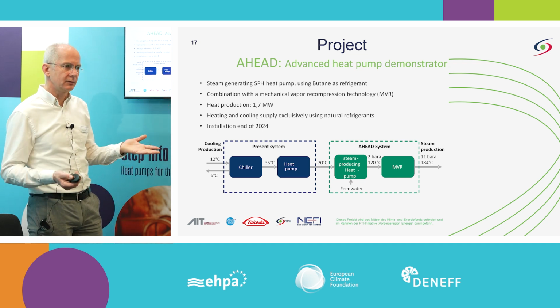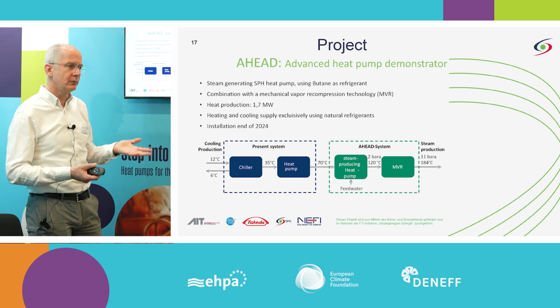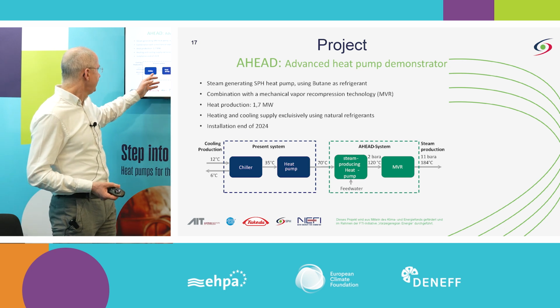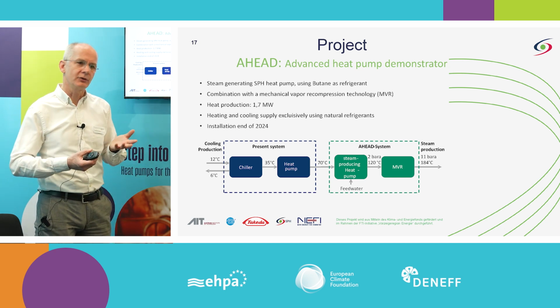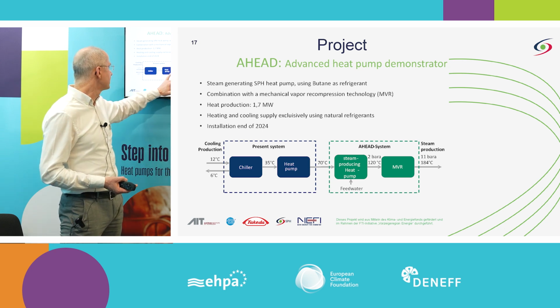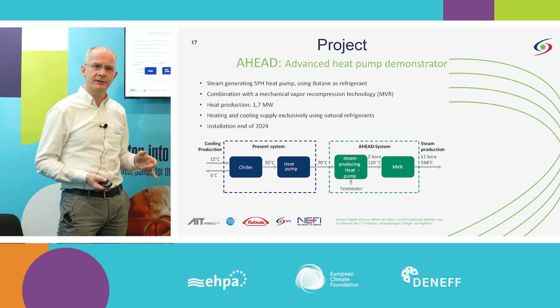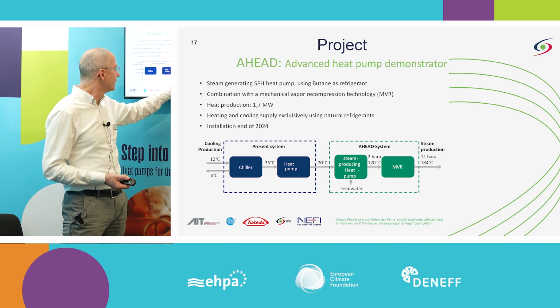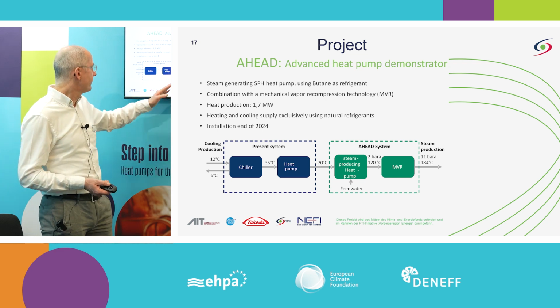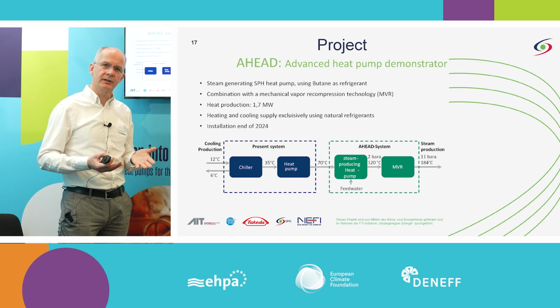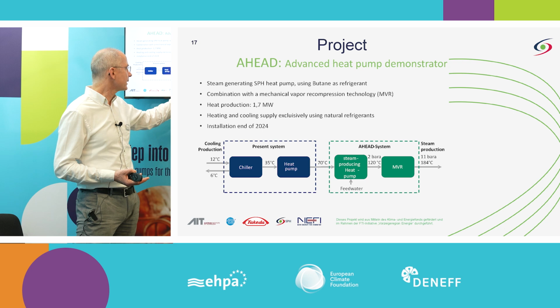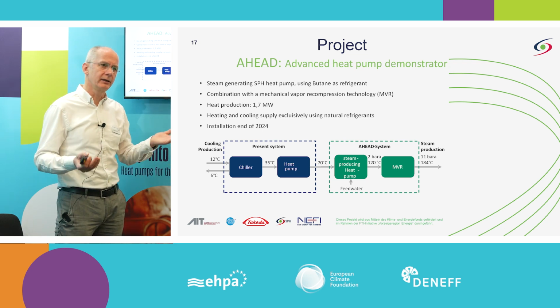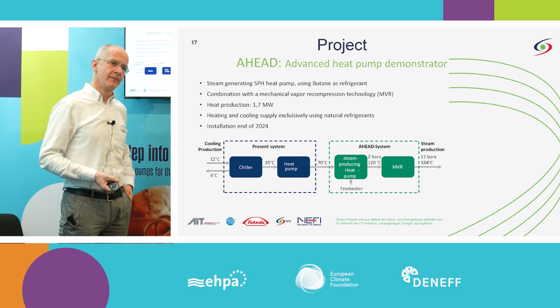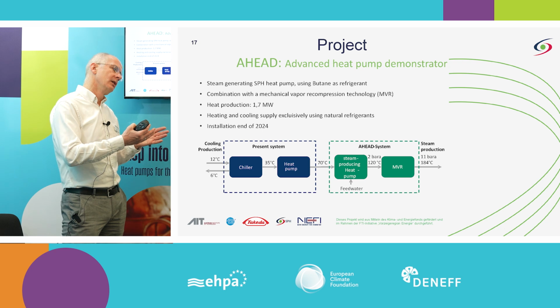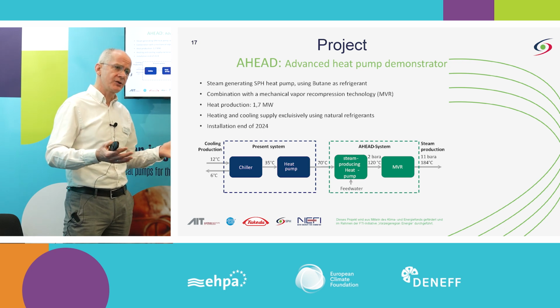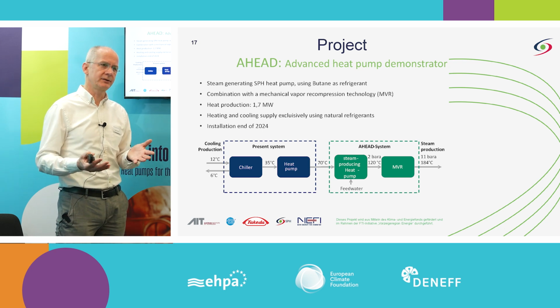What they already have, like many companies do, is a chiller system which is already existing. The heat from this chiller system goes into an ammonia heat pump, which is also already existing. From this ammonia heat pump, we receive 70 degree hot water. We produce steam at 120 degrees, so 2 bars. At the end, there is in addition an MVR system which brings the steam to 11 bar. We could go even higher if you added another stage of MVR system. This means we can clearly see that temperatures in the range of 200 degrees are possible to achieve without burning anything.